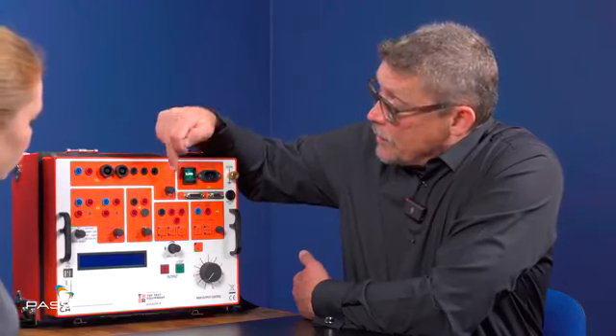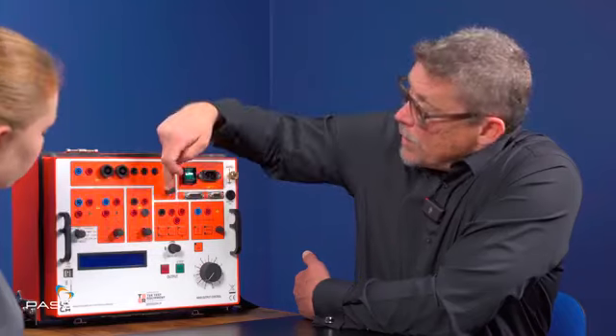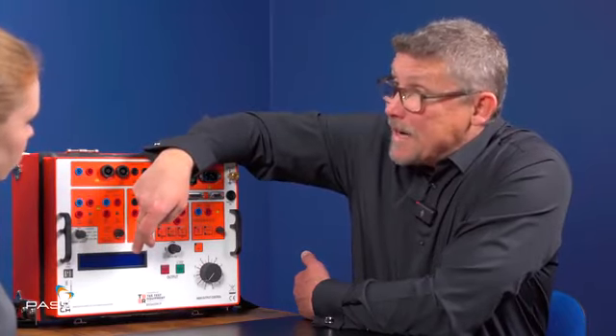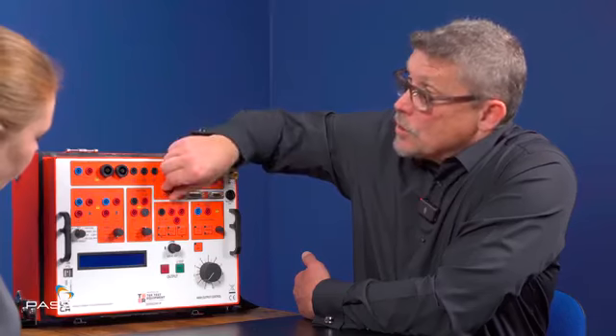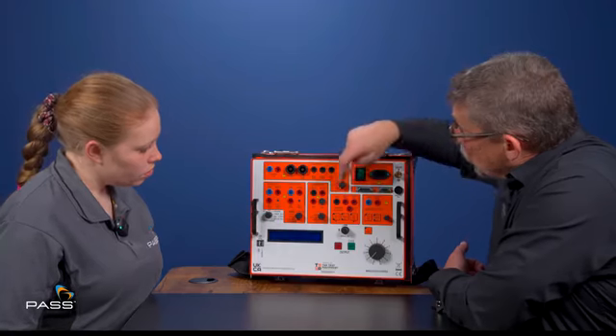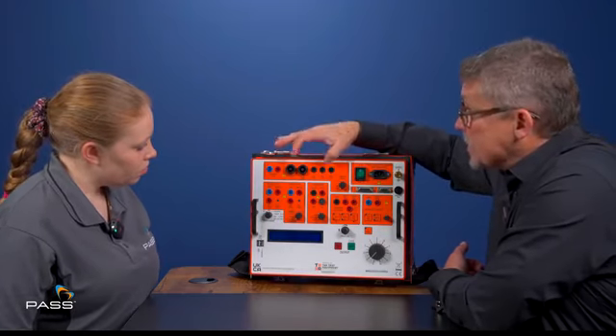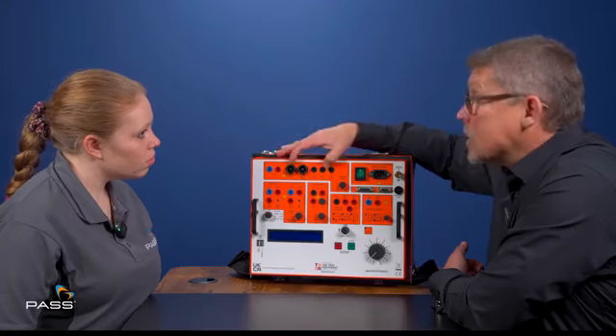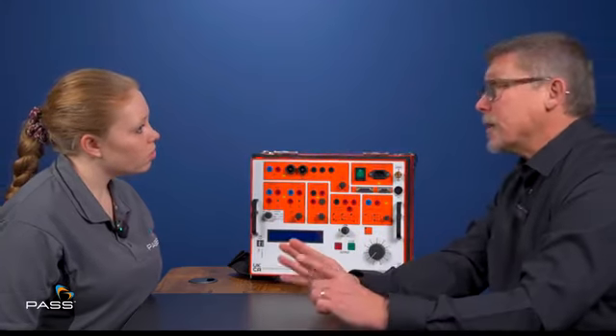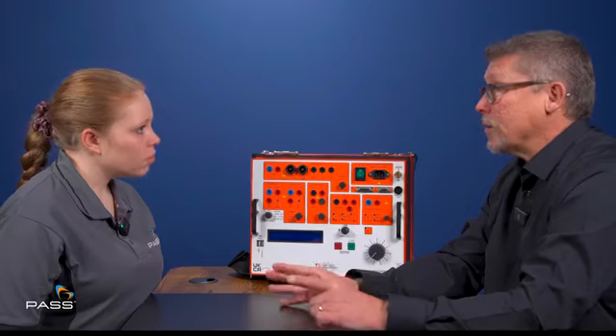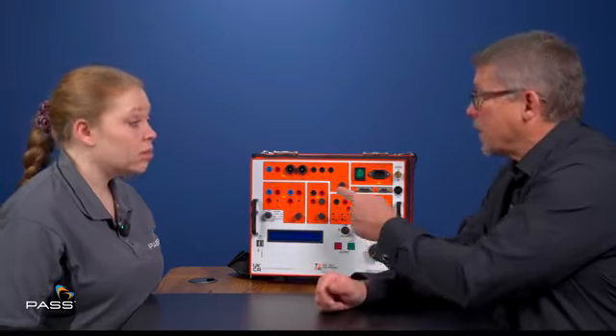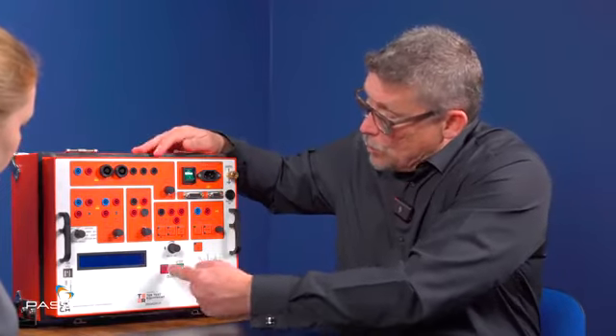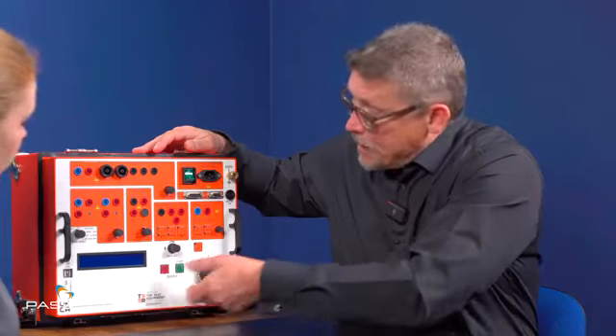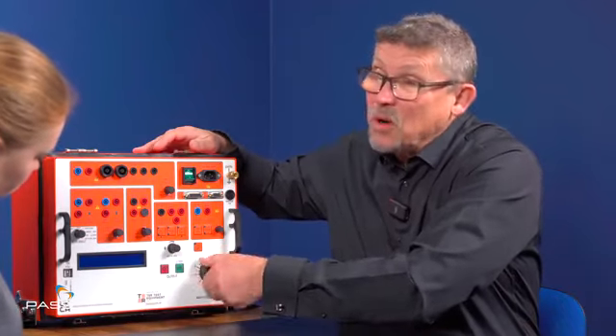It does two things. The first thing it will do is change the resolution here. So when I'm on 5 amps, I will get 1 milliamp resolution. When I'm on 200 amps, I'll get 0.1 of an amp resolution. When I'm on 5 amps, when this goes 10% above 5 amps, it will actually trip and stop. So if I've got a relay that's very, very sensitive and I shouldn't be putting too much current in, I can control or I can limit the current from here. The actual unit, when we output here, the current is turned on by hitting this on button, and then we control the current with a good old-fashioned variac.